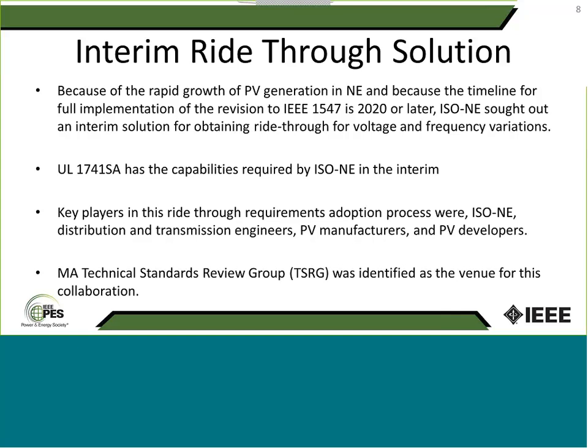What was the interim solution? The UL 1741 SA, or Supplemental A, was introduced as an interim solution. Just to give you a little bit of background on what 1741 SA is, California last year, I believe it was October 2017, mandated the utilization of smart inverters in California. So it was mandated by the California PUC. And utilities were concerned that, they had the smart inverter working group in 3 different phases. They came up with some requirements that were put in Rule 21, but the utilities were concerned that we really don't have any inverters that meet these requirements, that are certified and comply with these requirements, that pass some NRTL testing and so on.